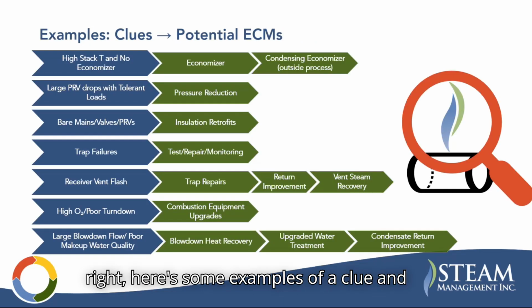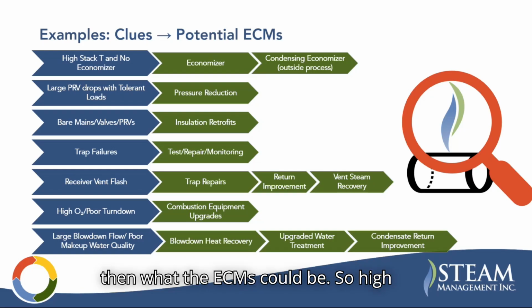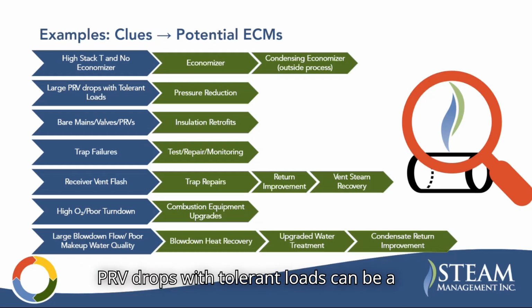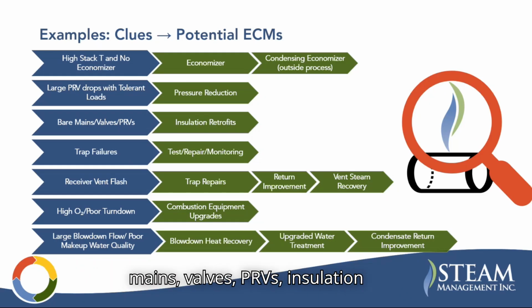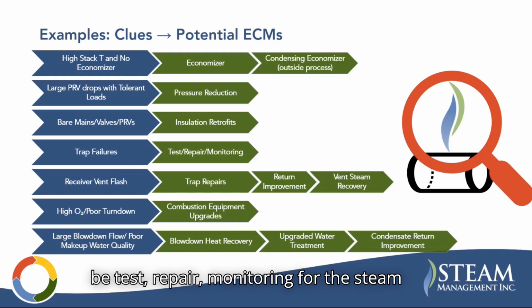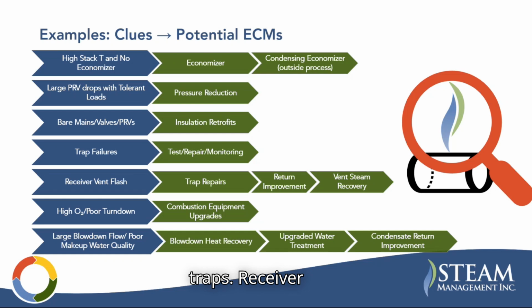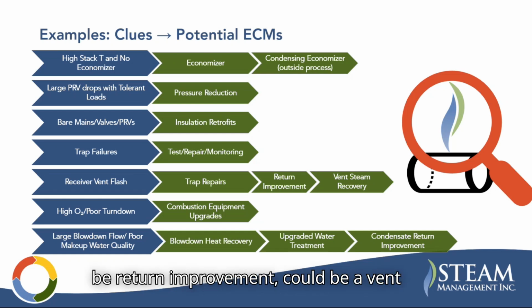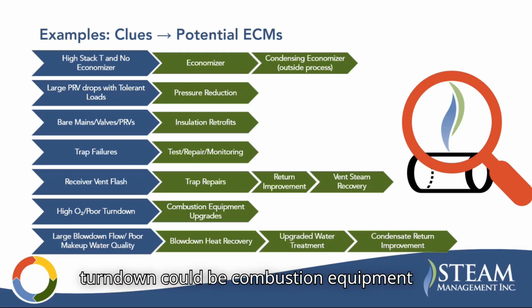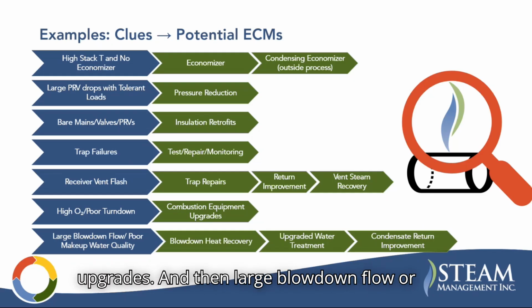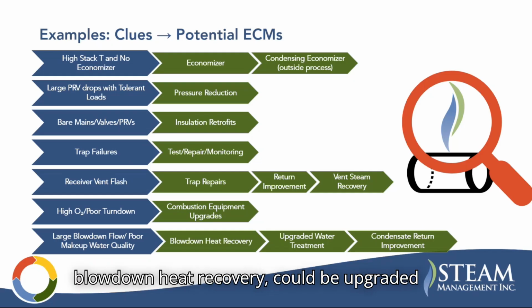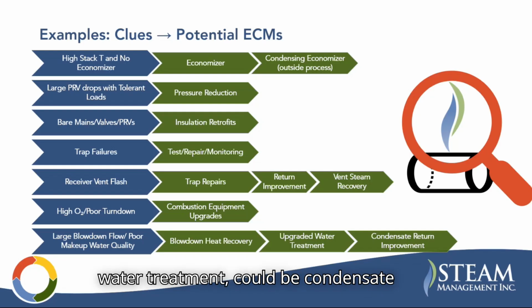All right, here are some examples of a clue and then what the ECMs could be. High stack temperature could be an economizer or a condensing economizer. Large PRV drops with tolerant loads could be a pressure reduction opportunity. Bare mains, valves, PRVs call for insulation retrofits. Trap failures are obviously going to be test, repair, and monitoring for the steam traps. Receiver vent flash could be trap repairs, return improvement, or a vent steam recovery, heat recovery opportunity. High O2 or poor turndown could be combustion equipment upgrades. And large blowdown flow or poor makeup water quality could be a blowdown heat recovery, upgraded water treatment, or condensate return improvement.